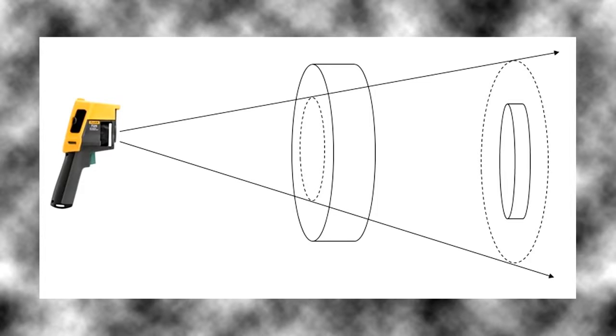In the second case, the target is smaller than the spot size, and any temperatures that are in that area will be averaged in with the temperature of the target.